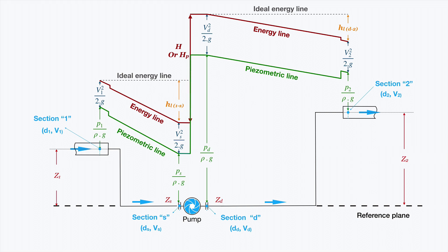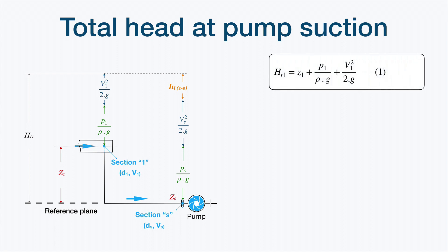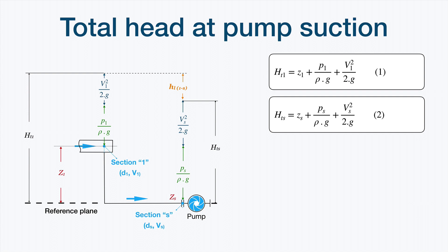The same happens with the piezometric line, joining the gap between the two points with a red line. Let's divide this graphic into two parts. First, we will see the total head at the pump suction section and the equations to determine the pump head there. The total head is equal to the sum of the geodetic head Z1, plus the pressure head P1, plus the kinetic energy — this is equation 1. At section S, we have the height Zs over the reference plane, the pressure head, and the velocity head.